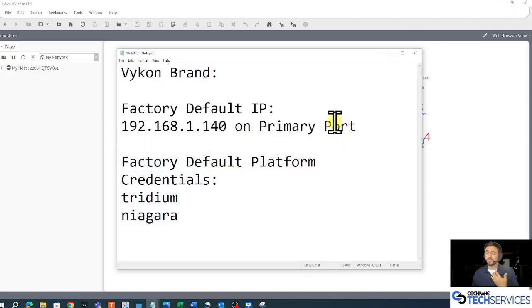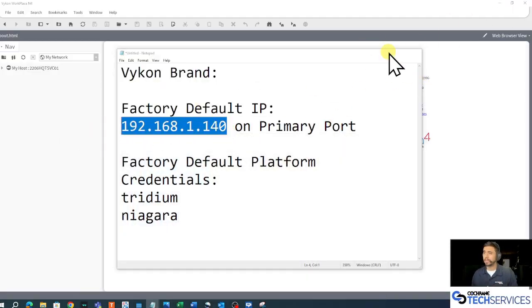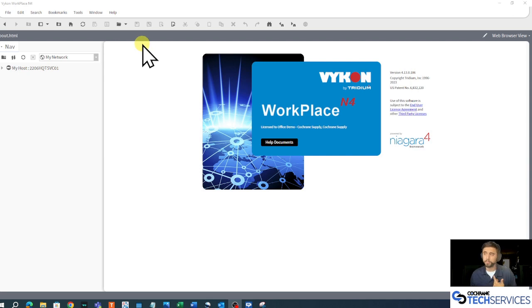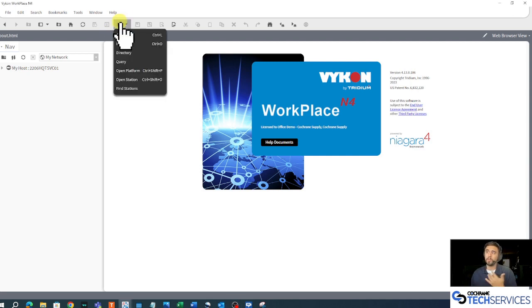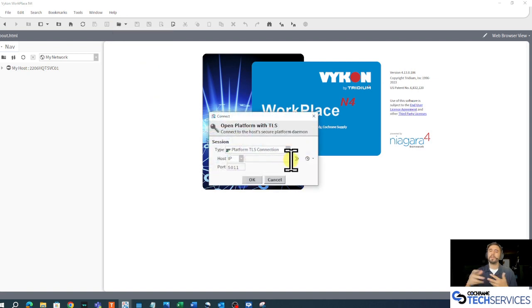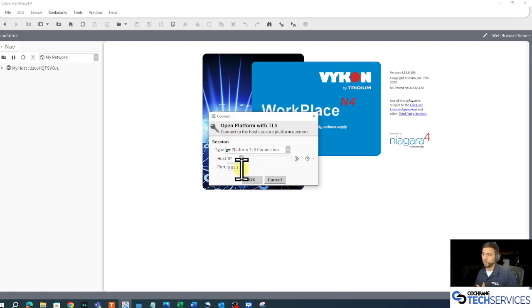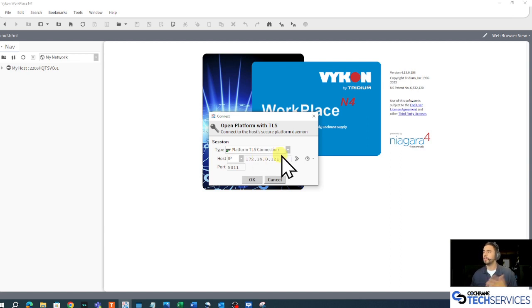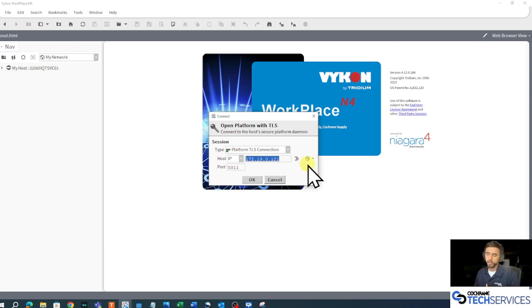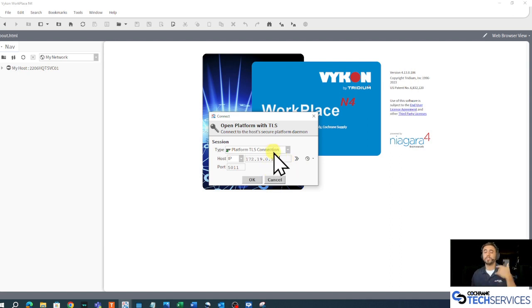My IP address is a little bit different from the factory — that's okay. The way I'm going to talk to my Jace's platform is to hit this little open folder button in my toolbar, go down to Open Platform, and connect using the platform TLS connection. That TLS connection over port 5011 means we're going to communicate securely using certificates. In the dialog box to the right of the host IP, I enter the IP address of the Jace I want to talk to, and click OK.